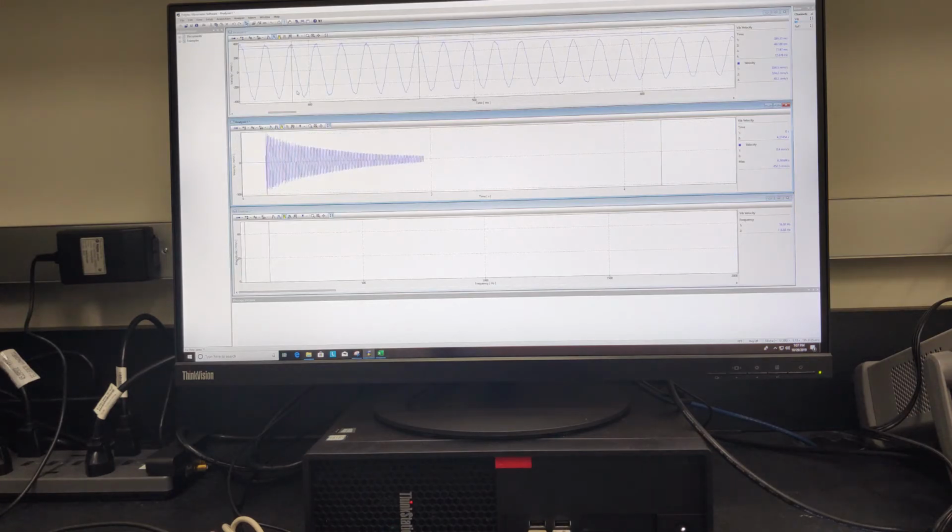In this part, we need to perform 10 impact tests with a peak velocity magnitude in the FFT domain between 15 and 60 millimeters per second. Accordingly, in the time domain, this is from about 100 millimeters per second to 400 millimeters per second.